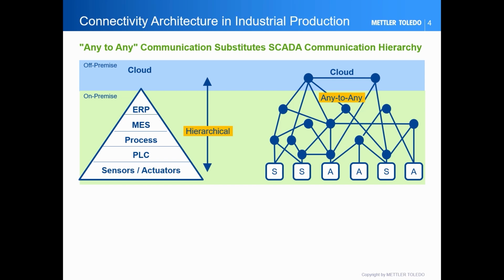Communication is via networks such as Profinet and Ethernet IP, but realistically also serial point-to-point connections such as RS-232 or even 4 to 20 milliamperes. On the right-hand side, you see the illustration of any-to-any, meaning everyone communicates directly with everyone. With any-to-any applications, sensors and actuators communicate directly, ignoring the strict hierarchy levels of SCADA. I have to point out, today time-critical data is not communicated via any-to-any, but this will change in the future.